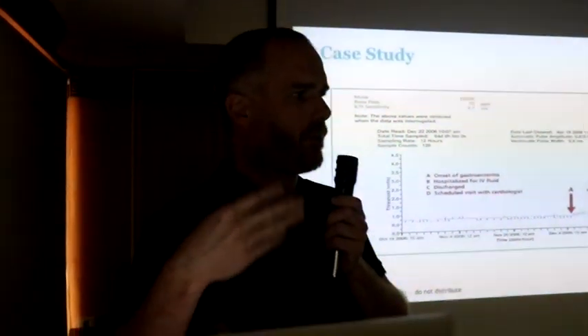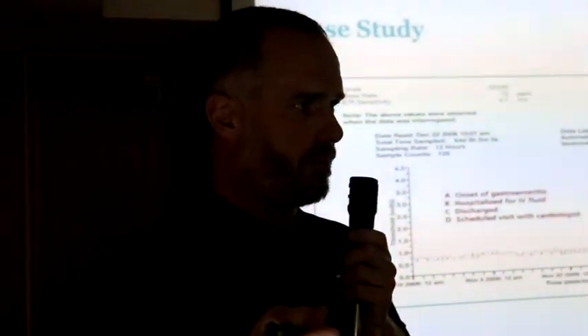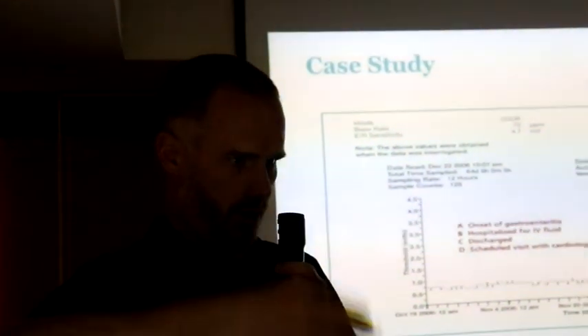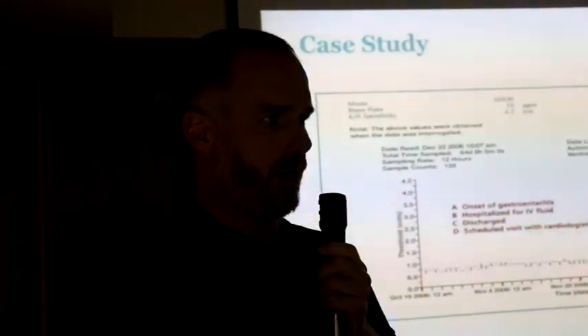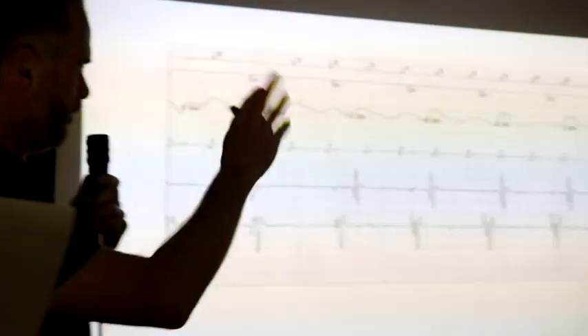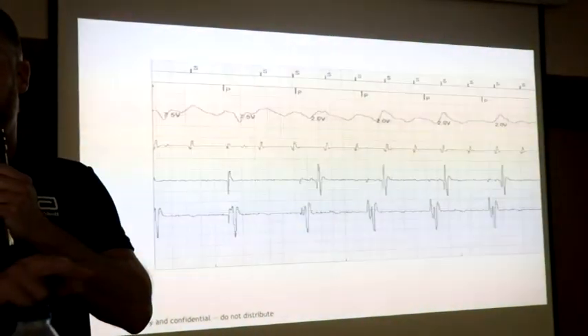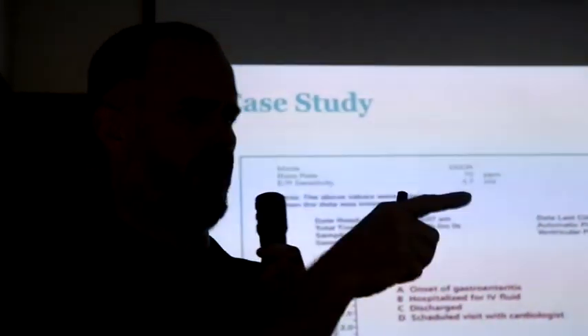We like to do that at implant, and other companies have algorithms like this. Some are beat to beat, some are not. The Abbott one is beat to beat. If it loses capture, it brings the threshold back up, and it gives you these lovely trends. It monitors the threshold beat to beat, but it runs the threshold test every 8 hours. When it paces, every time it delivers a stimulus to the ventricle, it checks: pace, check, and if it doesn't capture, a backup pulse is delivered immediately.